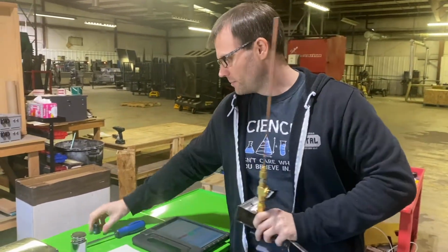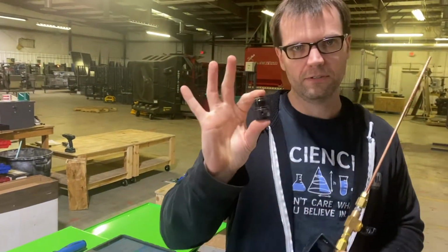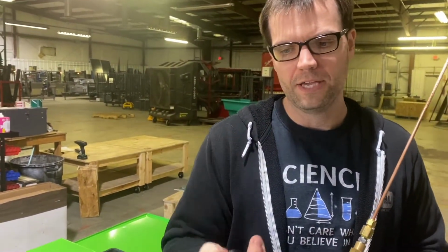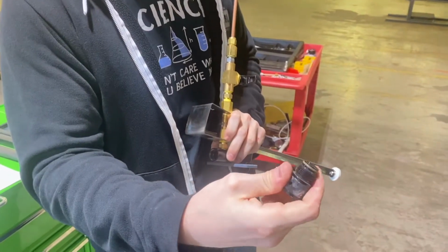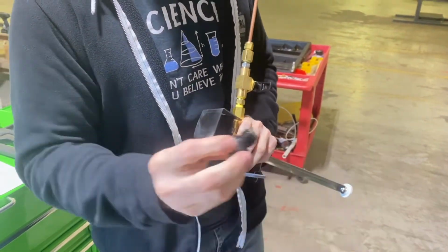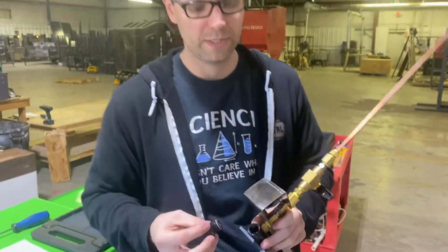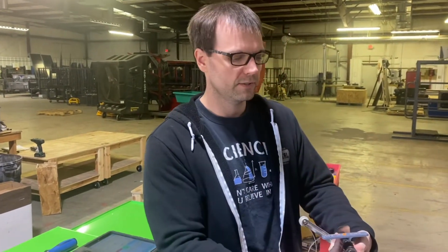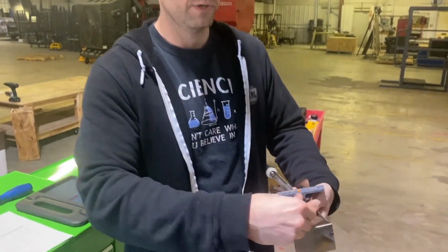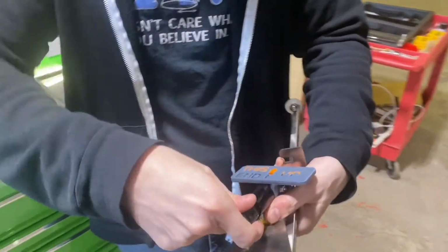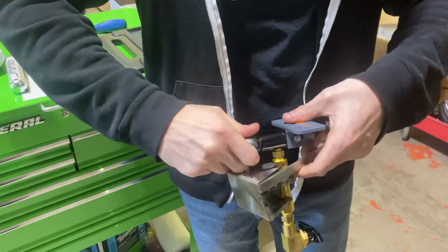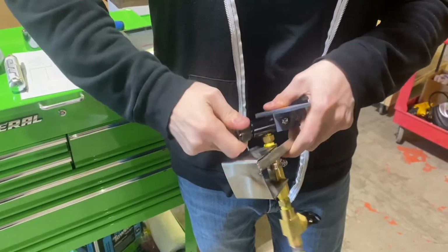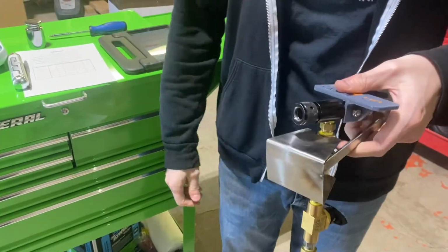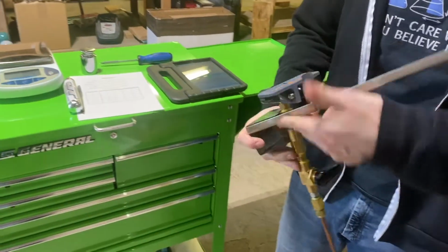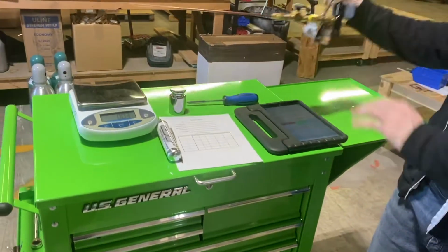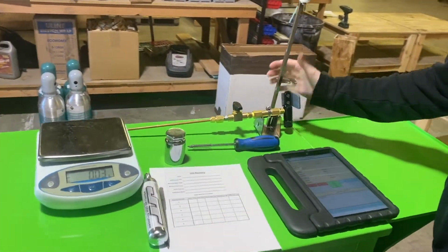All right, the next step, we supply several of these. These are just adapters, and they include an O-ring, which probably over time will degrade. And that's why we supply multiple adapters here. This just screws right onto the very end of the release device. And we want to screw it on until it's tight. You know, don't get a wrench or anything, but we just want to make sure it's hand tight and won't turn anymore. So we have that release device fully assembled and ready to go.